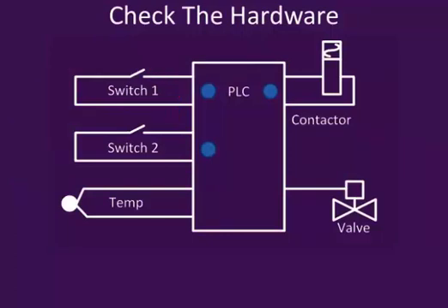Personally, I think that's a colossal waste of time. A simpler way is to simply close the switch and check the correct input comes on. So you close the switch and a light should light up on the PLC, or you should see something come on in the software. You can either use the LEDs, they all have them. A better option is to load a quick test program, just inputs and outputs, into the PLC and check through the software.